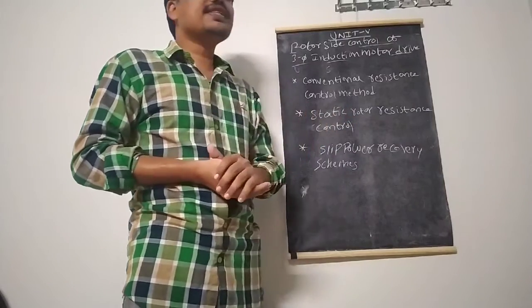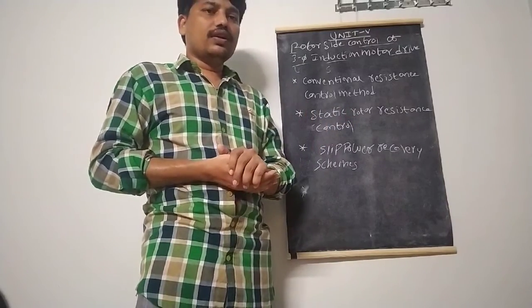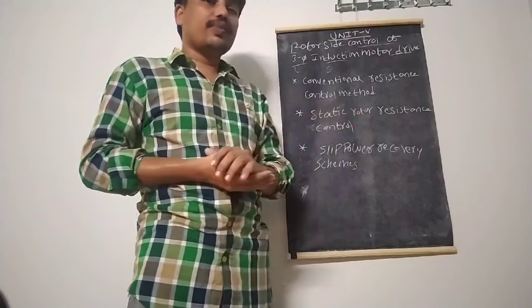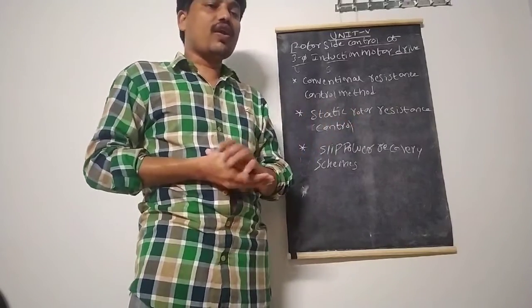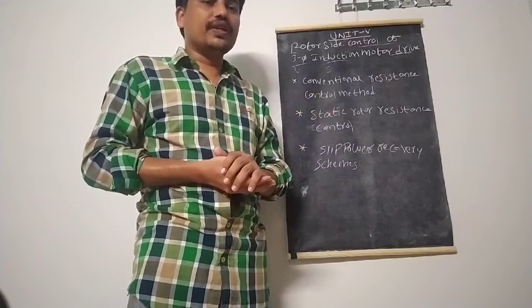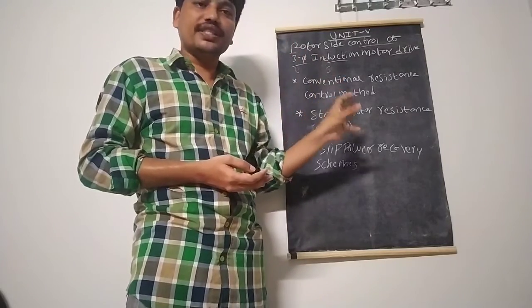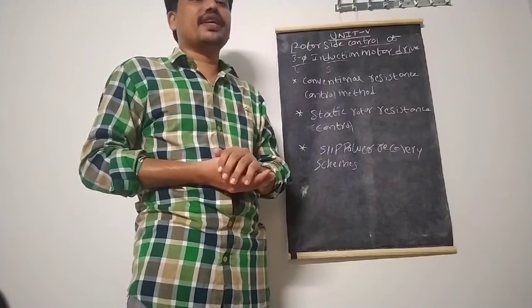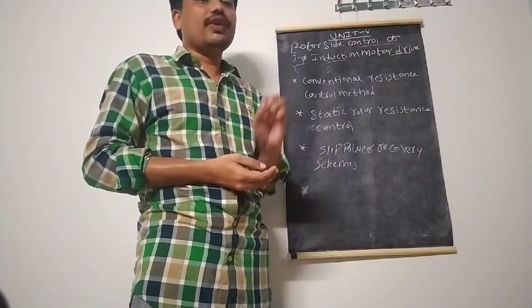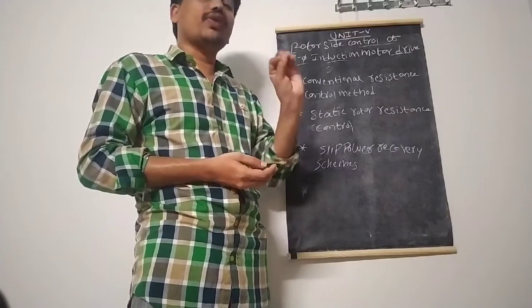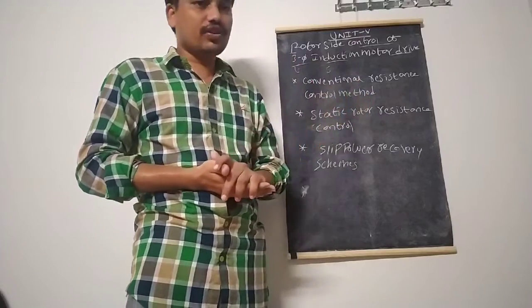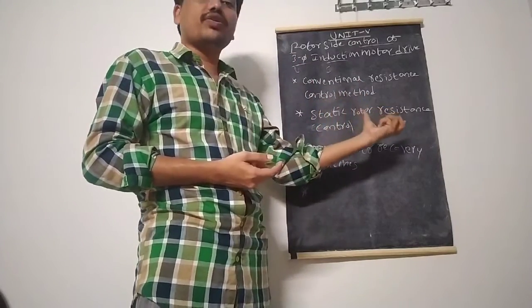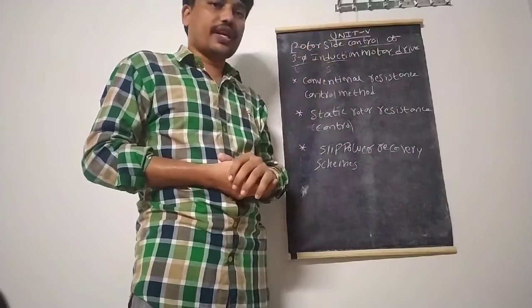The next method is the static rotor resistance control method. In this method, we do not control the resistance manually; instead, we control the static rotor resistance with the help of power electronic semiconductor devices — especially choppers. This is why in some textbooks it is referred to as the chopper resistance control method for induction motor drives.